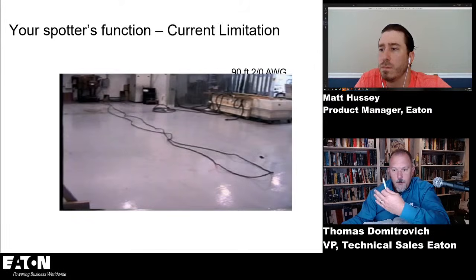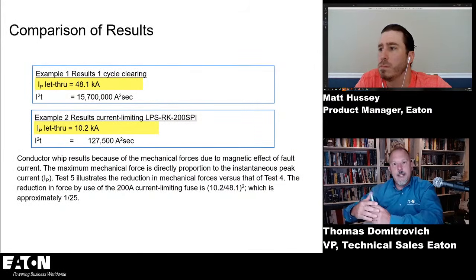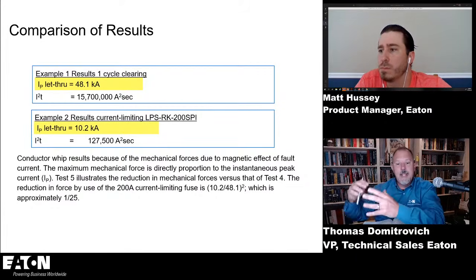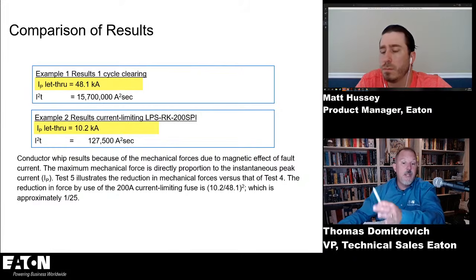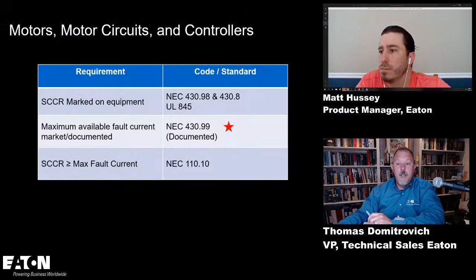So with that 1-cycle clearing time, in that case, you're less than a quarter cycle. You're translating into less magnetic forces on the power distribution system. We went from 48,000 amps peak to 10,000 amps peak, and from 15.7 million amps squared second to 127,000 amps squared second. So that's a big difference from a peak current perspective.